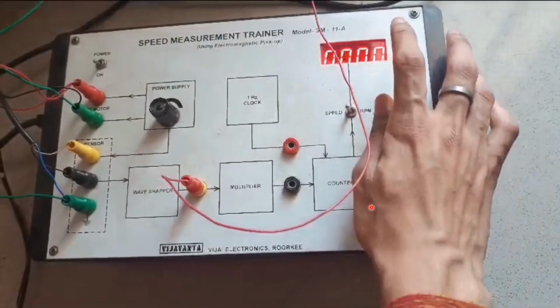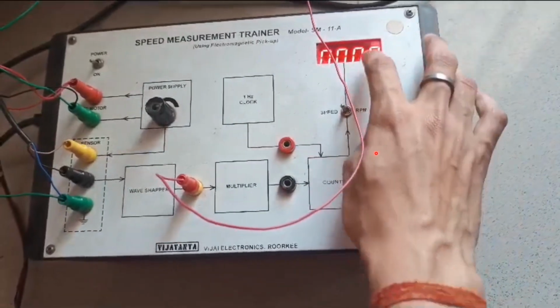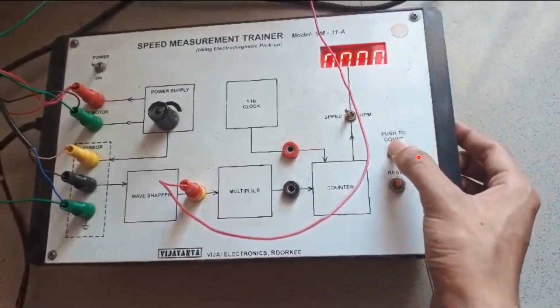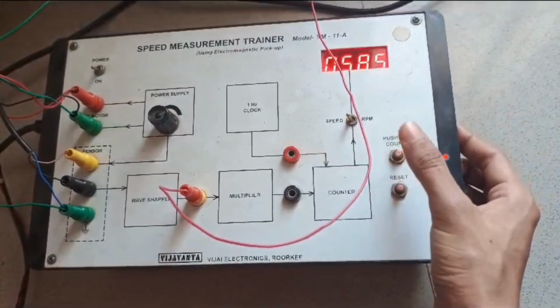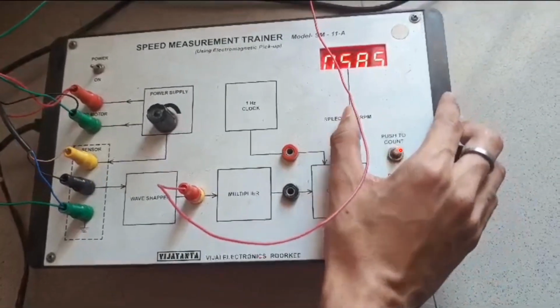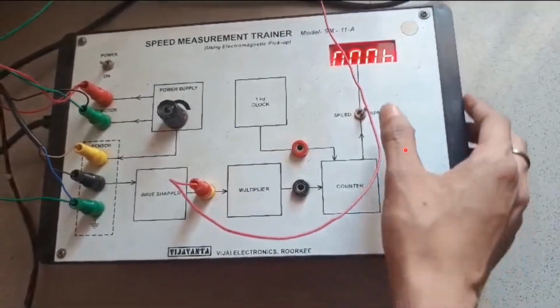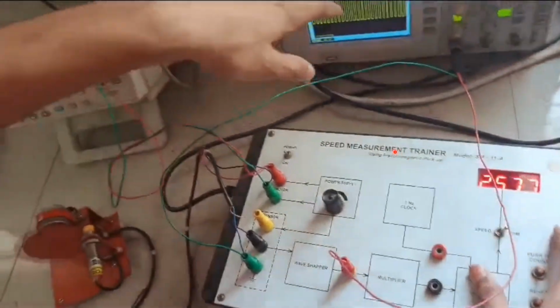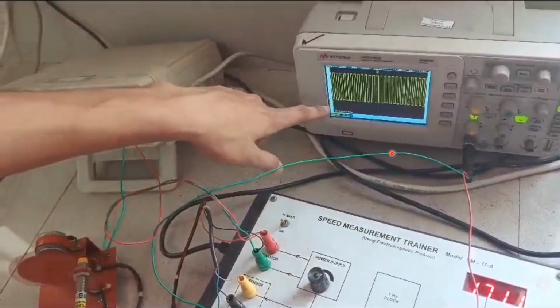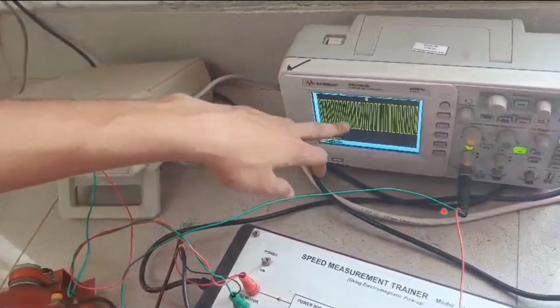There is a toggle switch which is shifted between speed and RPM. RPM is the actual speed that is measured, and this speed comes from the speed counter, which is sensed by the MPU sensor. This is the push to count button, and this is a reset button. This will change the entire reading to 0, and this is actually a timer.